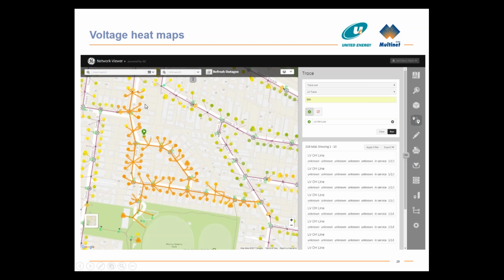We can see all the customers on that substation, and yeah, that's indeed all the orange ones, all sitting with overvolts. This very clearly highlights we've got an overvoltage problem or potential overvoltage problem in this area. It's one of the highest averages on our network, showing this transformer is potentially earmarked for tap down. We can use this information to build nice dashboards for the planners, looking at which substations are the biggest priority, the highest and lowest volts on the network, for their capital plan and planning for the next financial year.